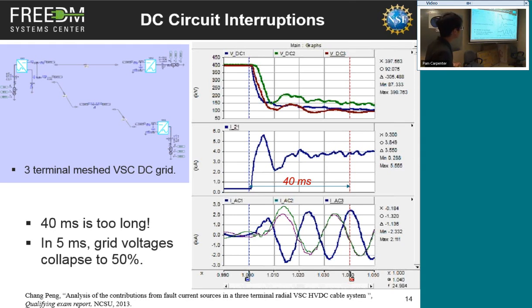So that's really too long. At that voltage level, the system doesn't really work. So your whole system is down. And if you have more voltage source converters interconnecting in a more complex DC system, gradually the whole system voltage will drop, and the system is down. The power transmission is interrupted. So 40 milliseconds is too long.